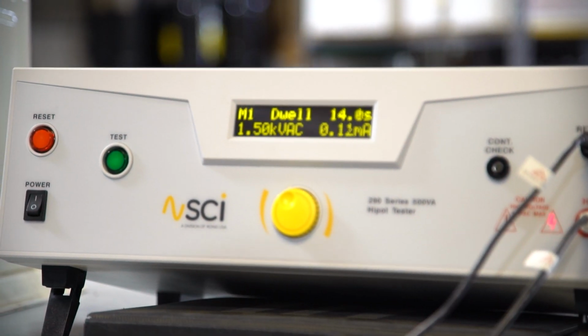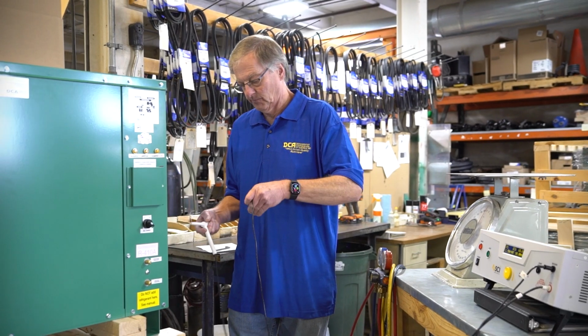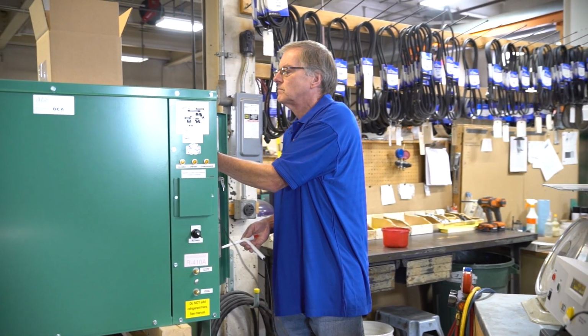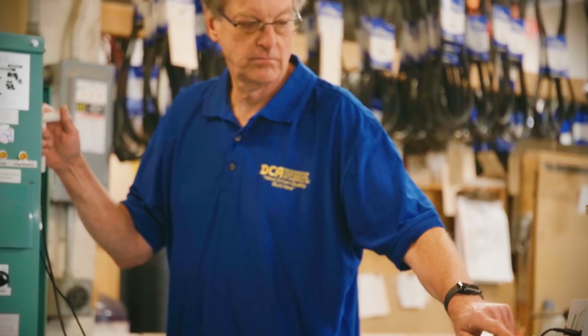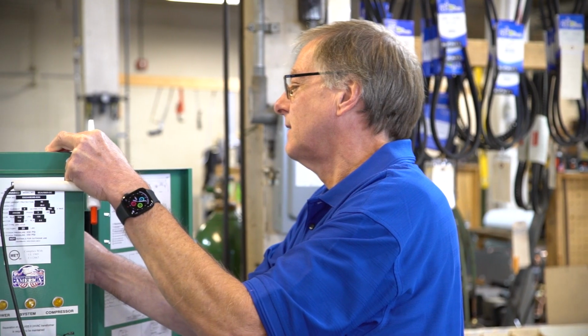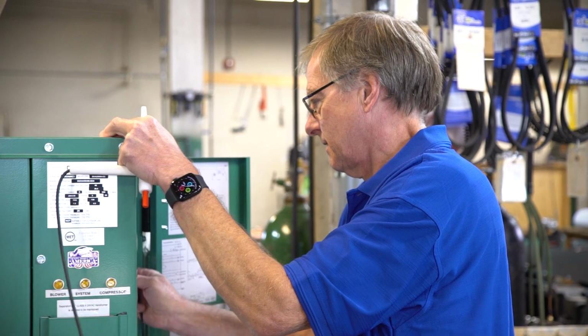What we do is put power to it and then check and make sure all the components are working. We also hook up a shroud to simulate the ductwork. We set the airflow to whatever the unit requires. We take an amp probe, check and make sure the motor is drawing the right amount of amps. We check the compressor, make sure that's working.